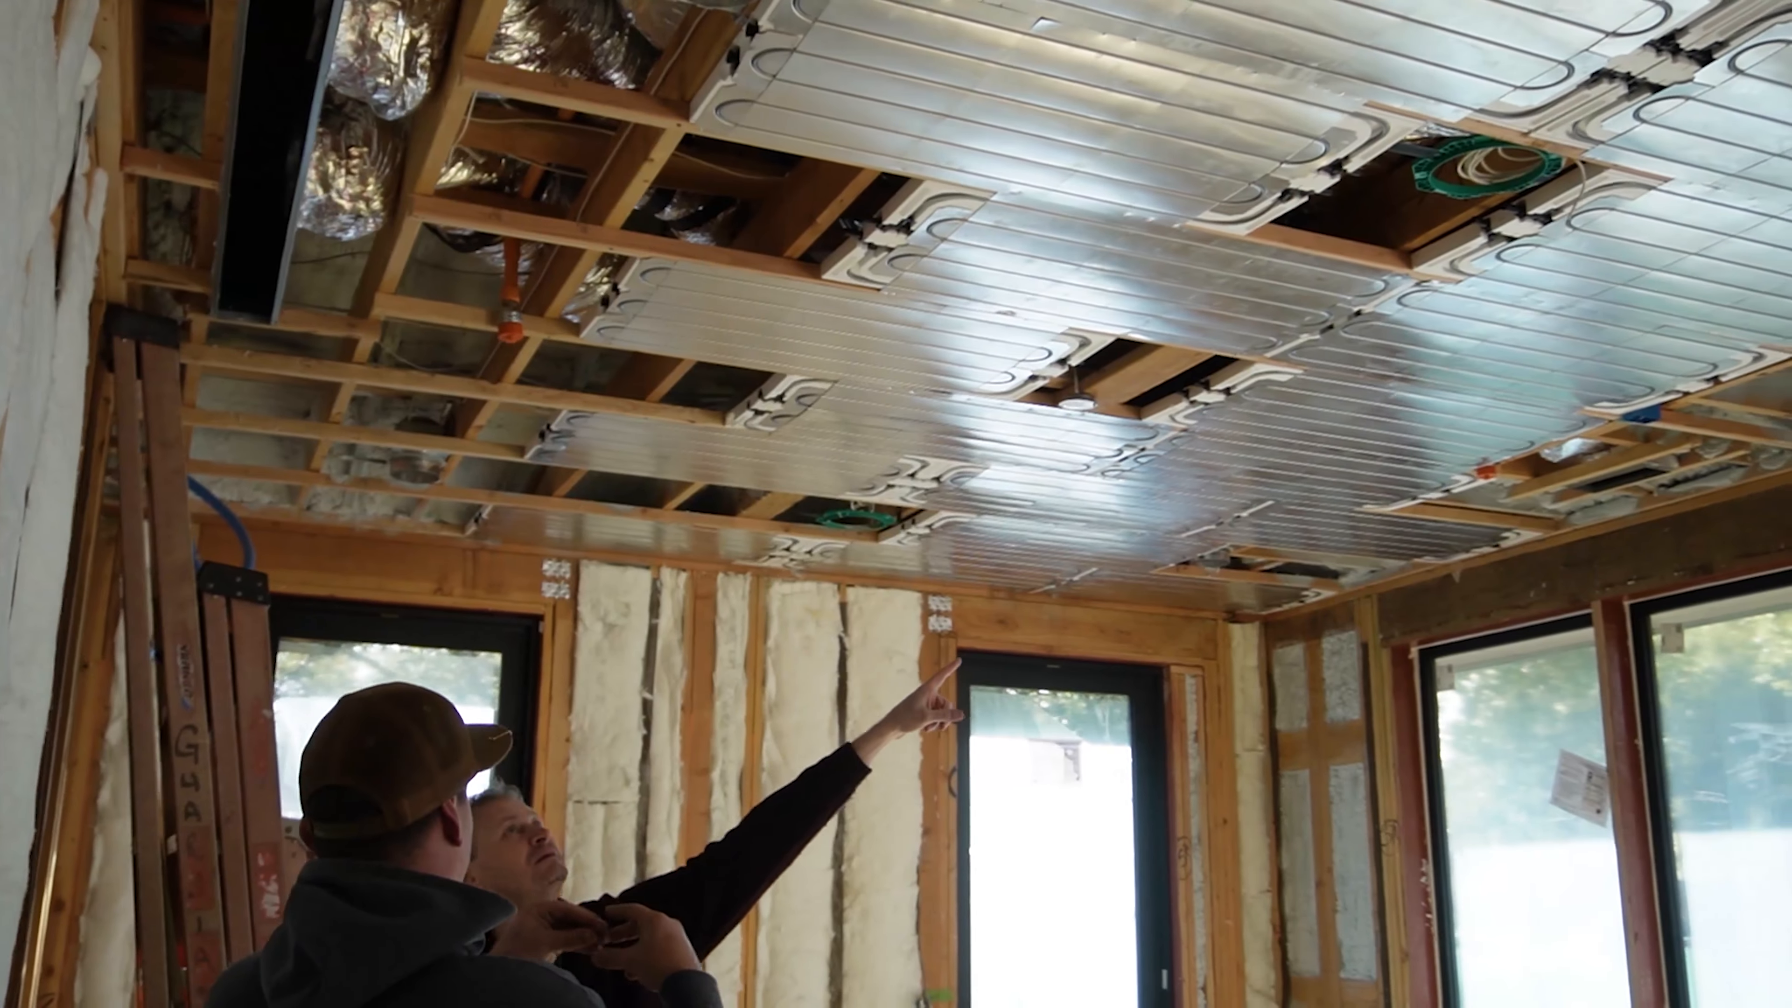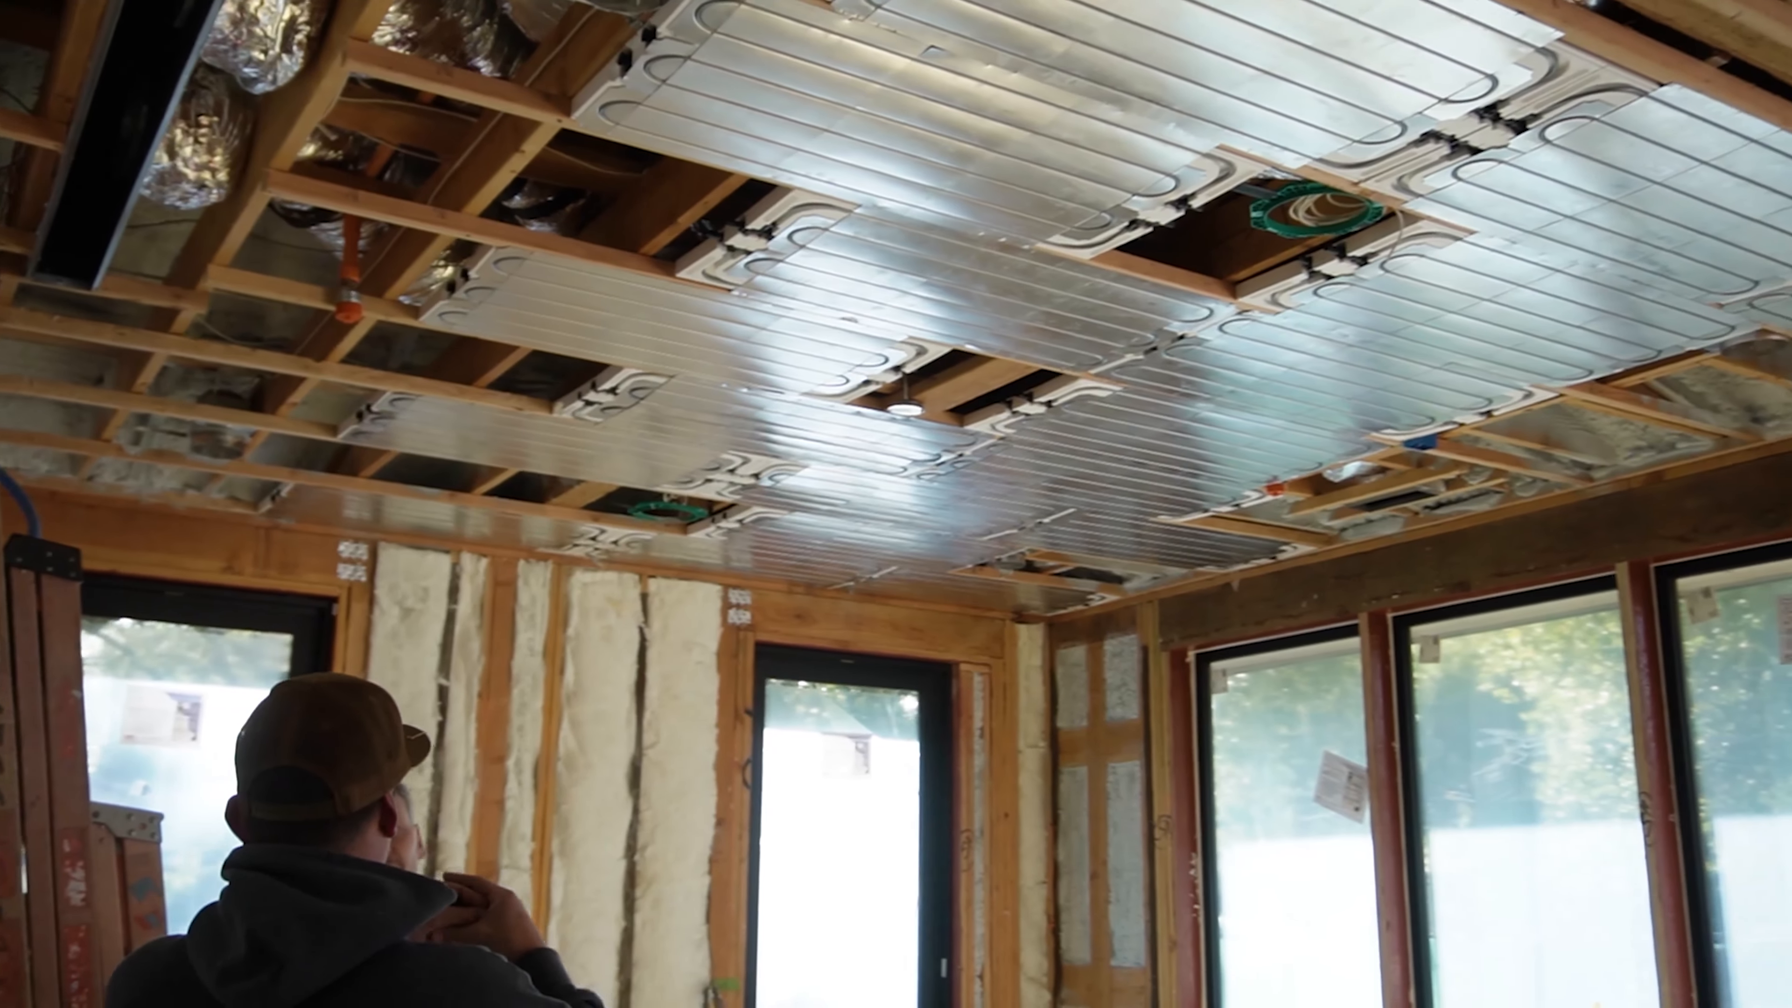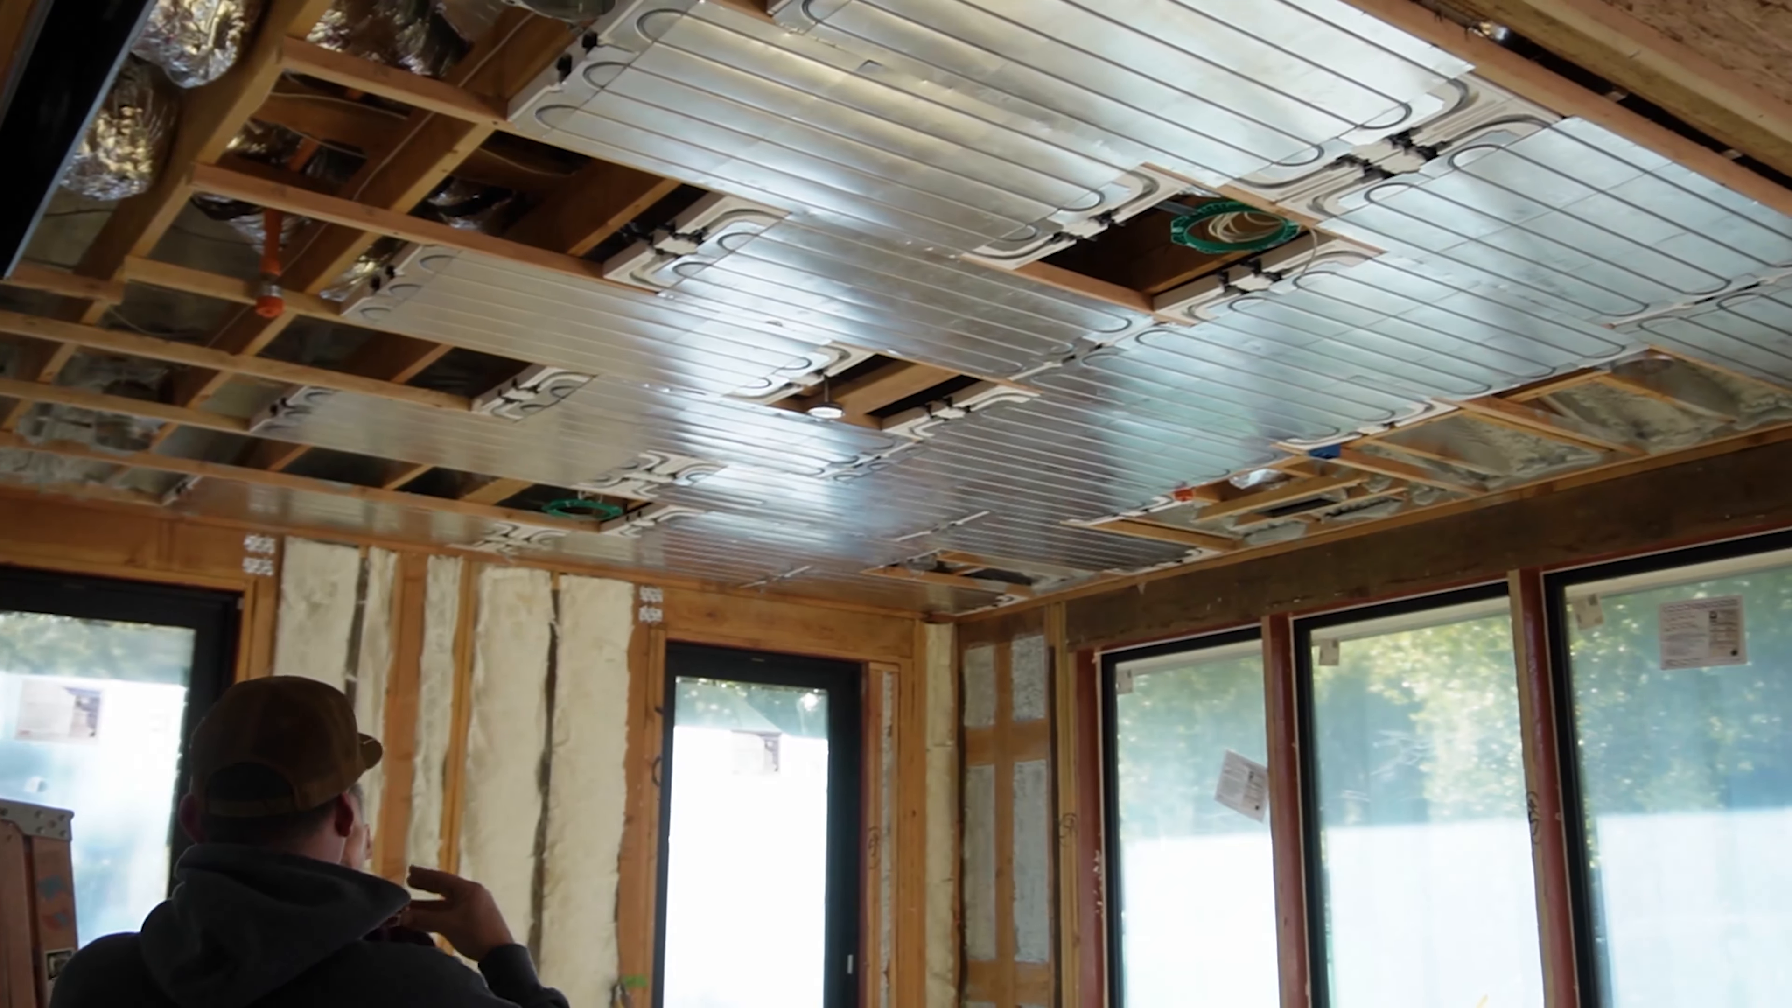And all these are good systems, but when you compare them to a radiant ceiling on the job site, they create more of a hassle where other trades might have to avoid working in a certain area because the floor is a big concrete slab right now, or there's piping all laid out. You have to be careful with a radiant ceiling. You're putting the radiant surface in the ceiling is out of the way, and you could typically do so much faster than you can with a radiant floor. And so you actually might save money by streamlining your job site through the use of a radiant ceiling.